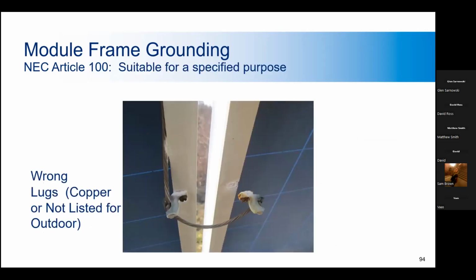Here's an example where a contractor attempted to accomplish bonding requirements with copper lay-in lugs on aluminum frames. You can see that they've corroded and actually broken away from the module. Also notice the reaction between the copper conductor and the aluminum frame in the upper left here. Do you think that these two modules are effectively bonded together? I think it's pretty obvious that the answer is no.